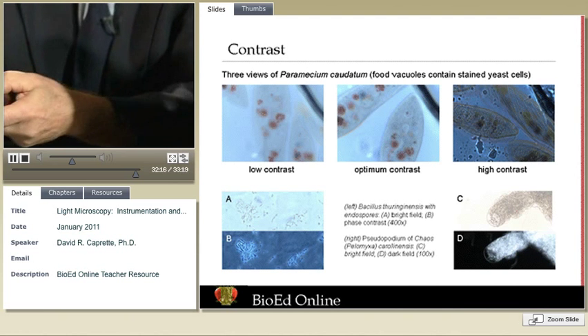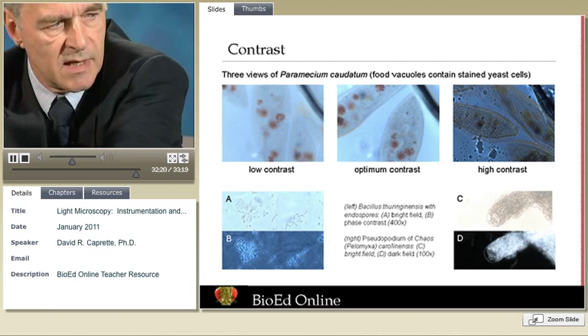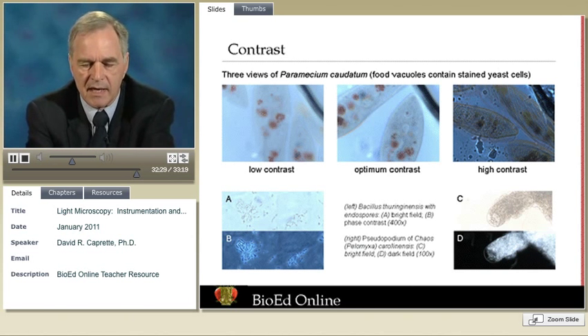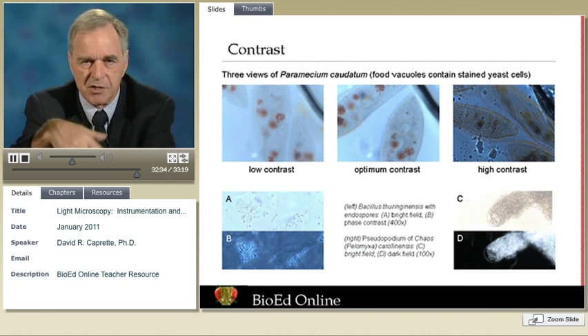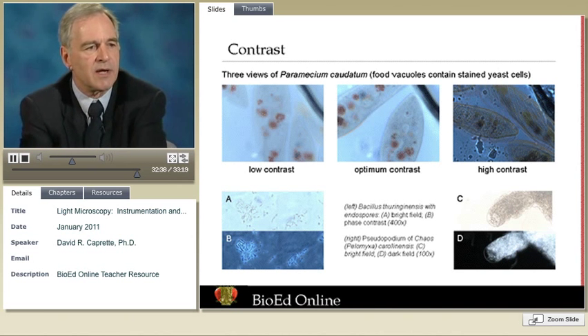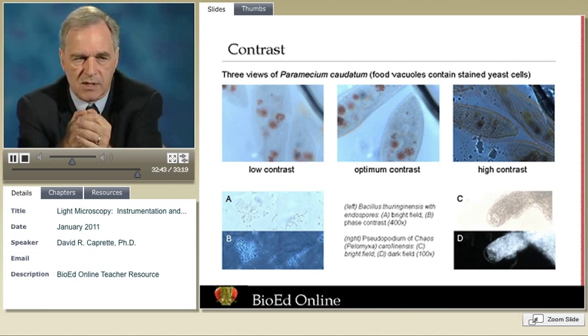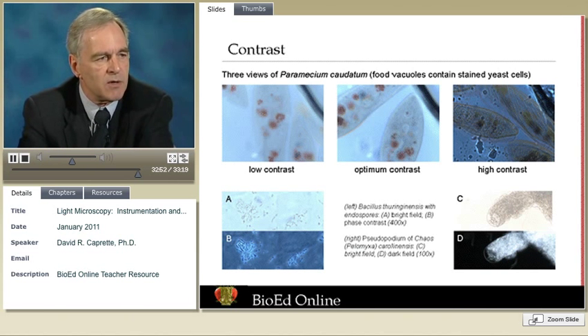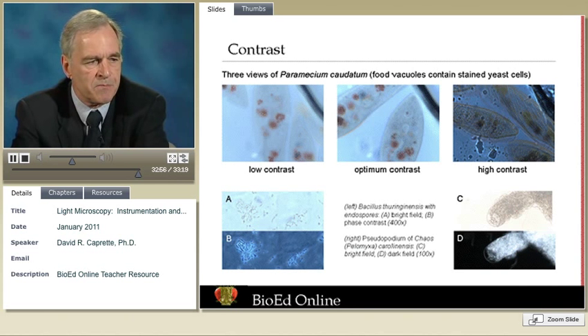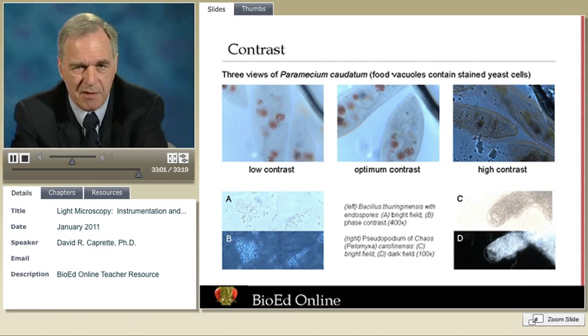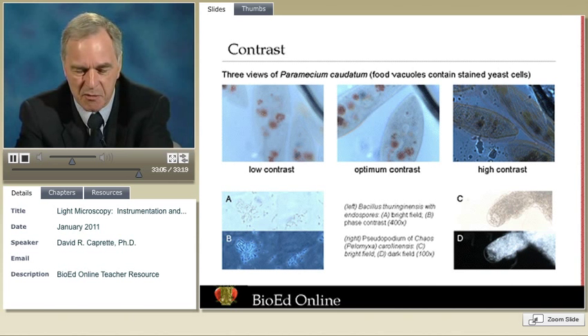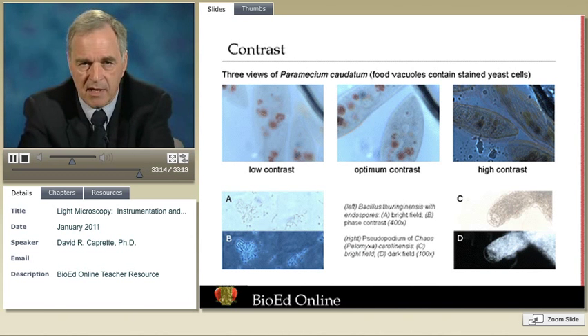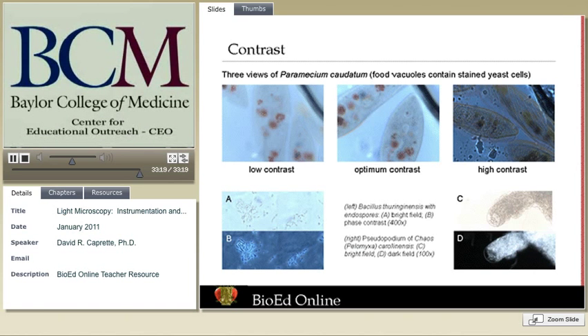What we want to do with objective lenses is optimize contrast with the compound microscope — have just enough contrast to see detail, but not so much that we distort the image. If you crank it down too far, you get double images sometimes. You can see fairly good views of the organelles of the paramecium under optimum contrast. With something like a large amoeba, which is one of the only ones visible in a bright field microscope, you might have to really crank down the contrast and over-contrast in order to see it at all. That's where specialized optics are preferable.